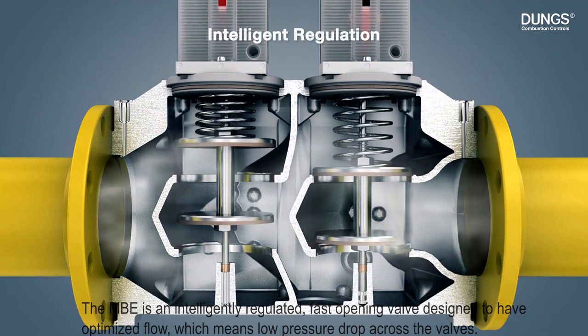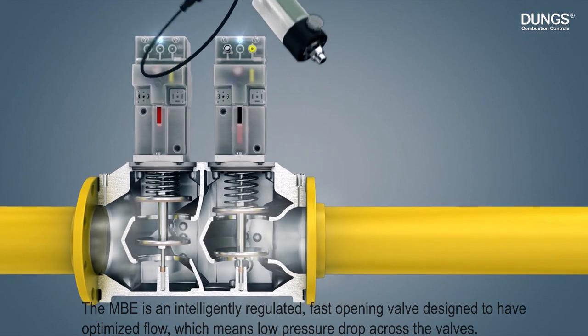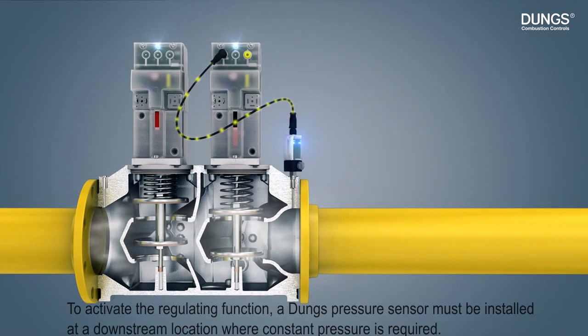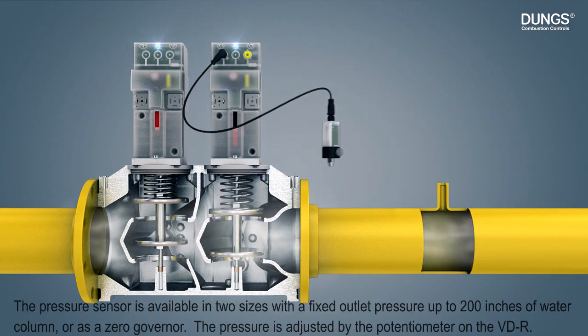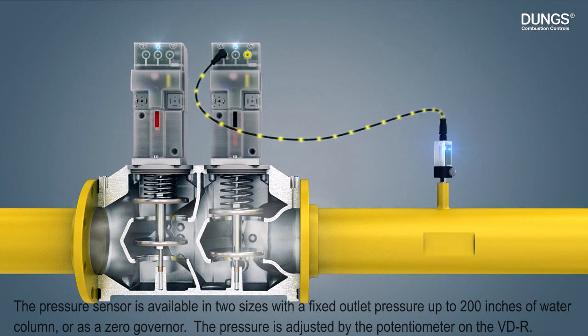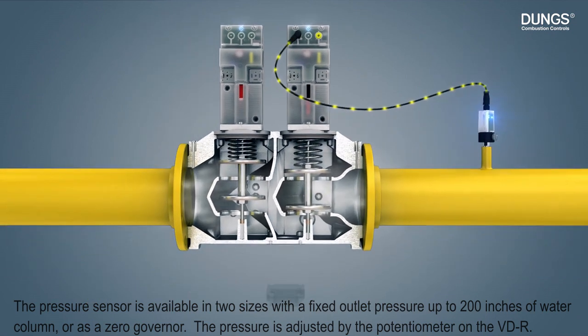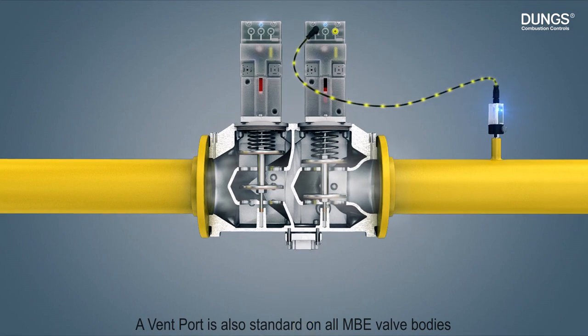The MBE is an intelligently regulated fast-opening valve designed to have optimized flow, which means low pressure drop across the valves. To activate the regulating function, a Dungs pressure sensor must be installed at a downstream location where constant pressure is required. The pressure sensor is available in two sizes with a fixed outlet pressure up to 200 inches of water column or as a zero governor. The pressure is adjusted by the potentiometer on the VDR. The vent port is also standard on all MBE valve bodies.